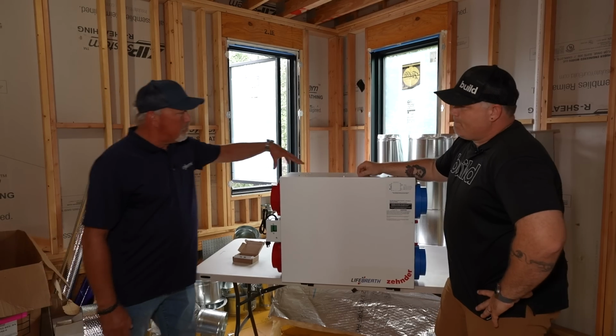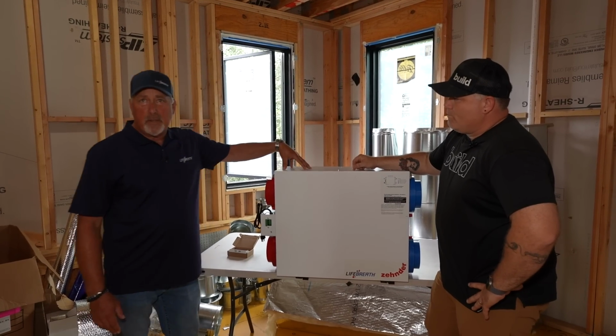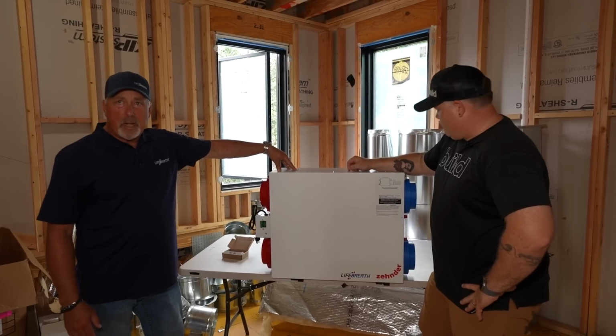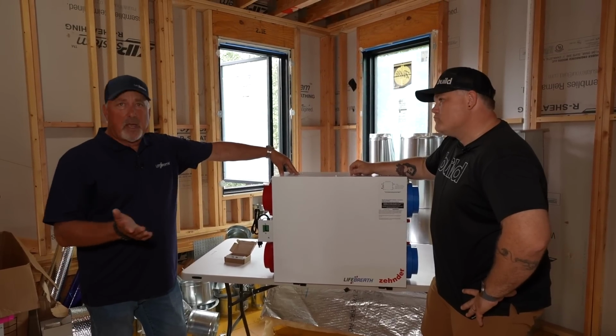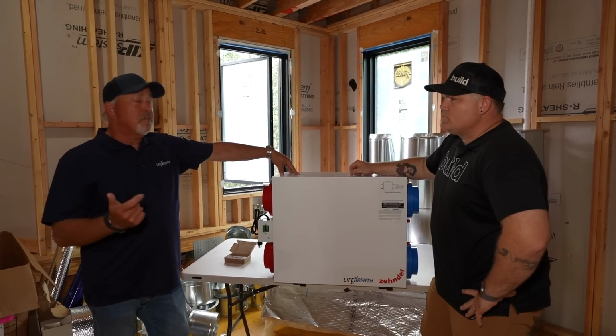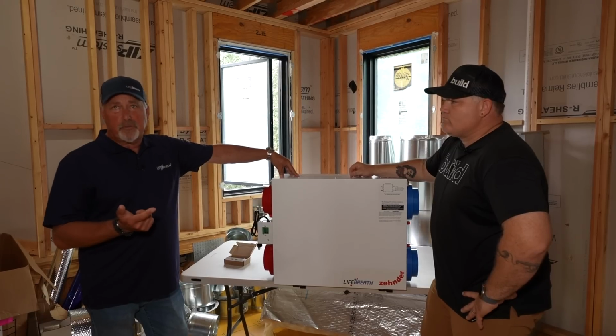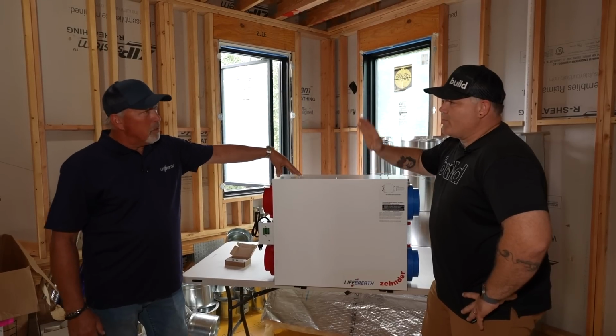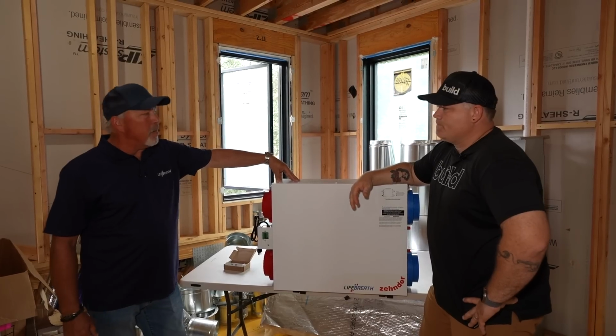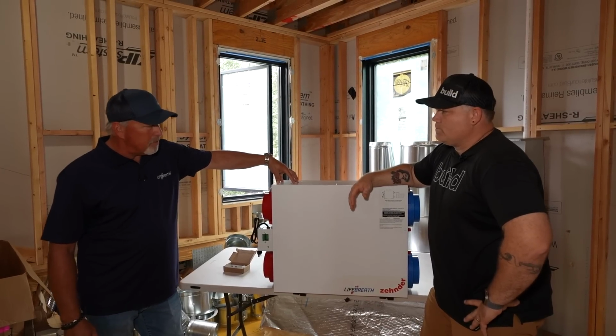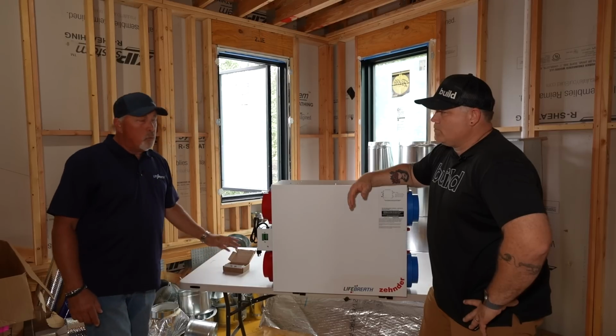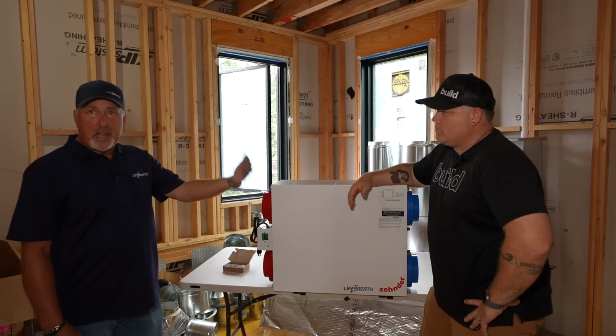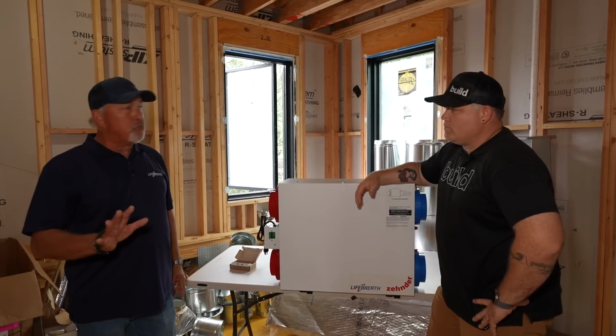How is this getting balanced to lead to the exact right amount of air? Okay, so this has got ECM motors in it, so it's highly efficient. We also have auto balance with these. ECM motors are fabulous - first of all, they don't use a lot of energy, and second, we can do lots of different control with them. You can ramp them up, ramp them down. So what happens with auto balance is, through the control, we set it up for the CFMs at each speed.